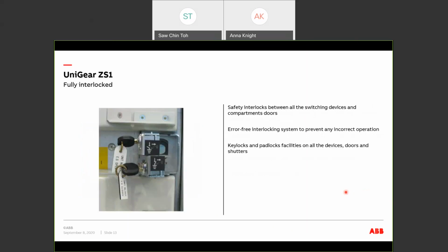The cable compartment at the front is also an interlock controlled compartment. You can only open the cable compartment after the circuit breaker is isolated and the cable is off. We have implemented all these error-free interlocking systems to prevent any incorrect operation. All the operating flaps, doors, and shutters will have padlocking facilities available as standard.